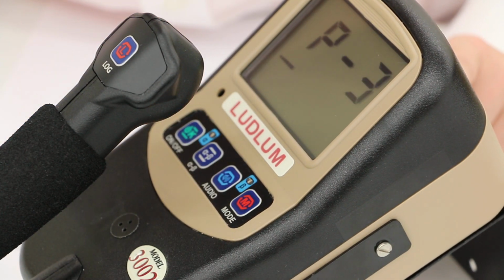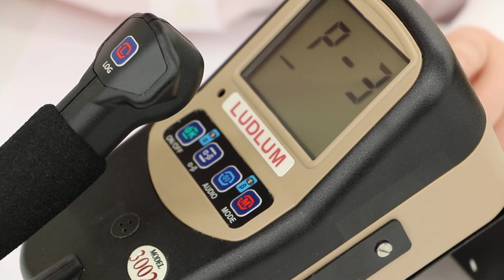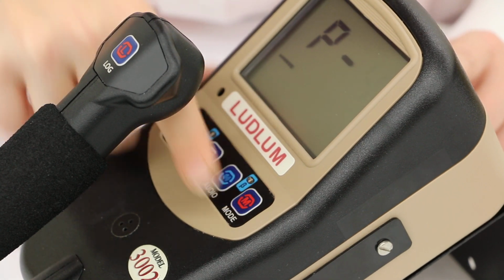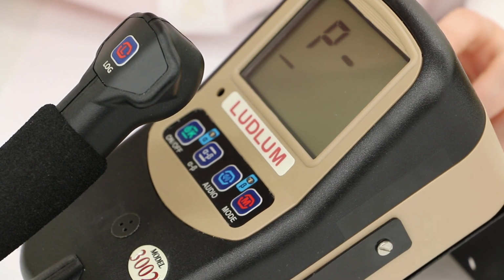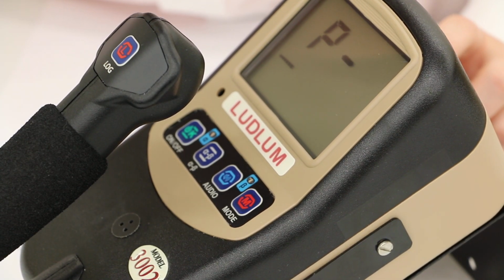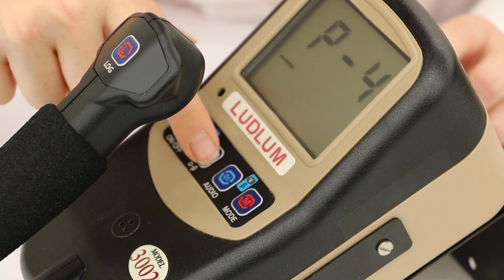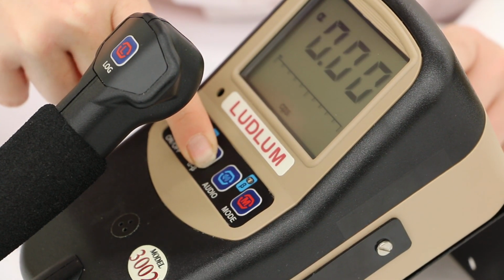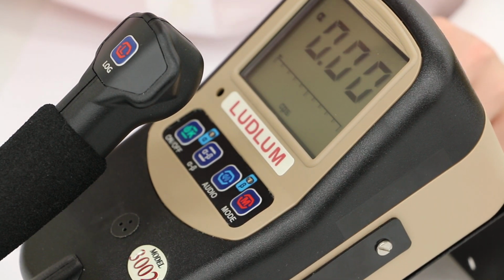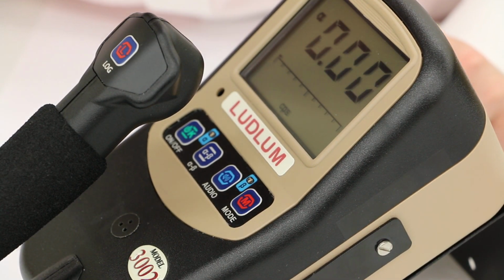Page 3 contains the alpha specific parameters like the threshold and window and alarm points. And page 4 contains the beta specific things like the threshold, window, and alarms. Holding the alpha beta button for 5 seconds will exit the menu completely. You must exit the menu properly in order for any changes to be saved.